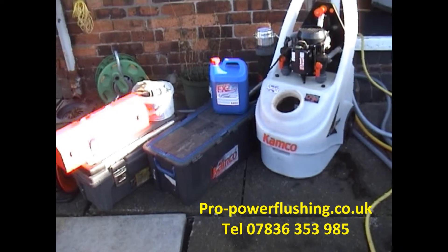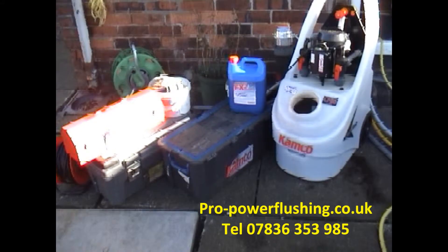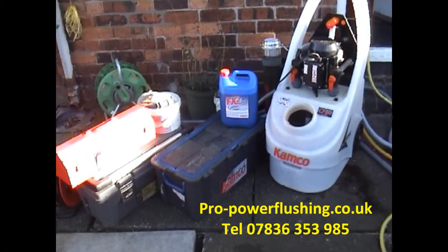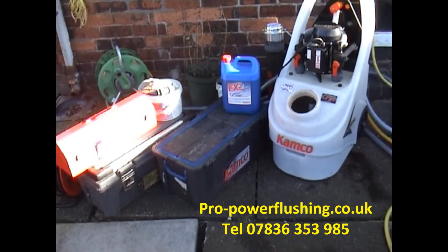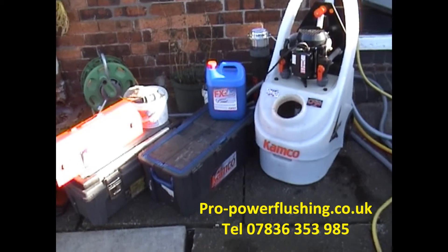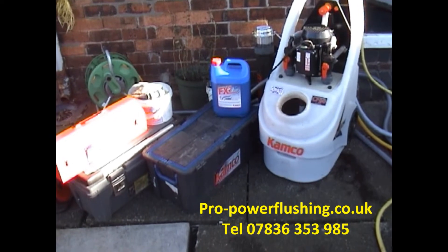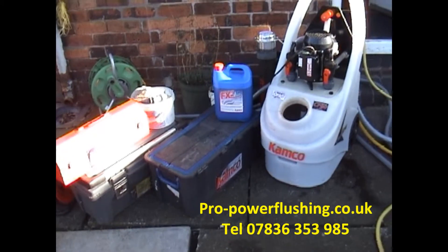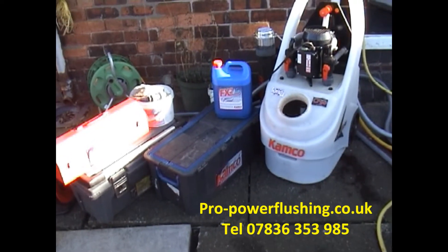By the same idea, if you're getting a new boiler and you don't think the system's been power flushed properly, just give me a call and we'll come and power flush it for you. It just doesn't make sense to fit a new boiler without a really first-class power flush. The power flush is all certificated to BS standard, pH and TDS levels taken, and Sentinel X100 inhibitor added after the power flush. Basically, it's all done 100% properly.